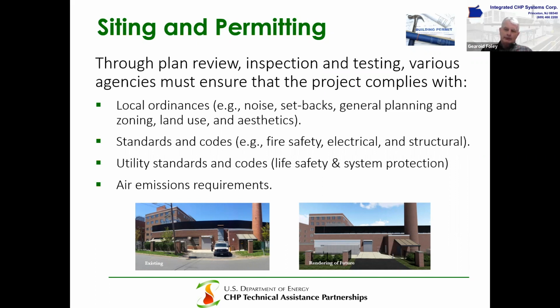Again, as long as you're ahead of it, it really doesn't become an issue. Do recognize noise and setbacks, and in particular noise, particularly at the neighbor property line, is usually where it's measured. Again, this has to be incorporated, and the earlier you do it, the better. You can pretty much get to any noise level required through various treatments to the equipment housing and the exhaust system. Just be aware of it up front. It's not a problem. If you have to retrofit something, then you've got a problem.